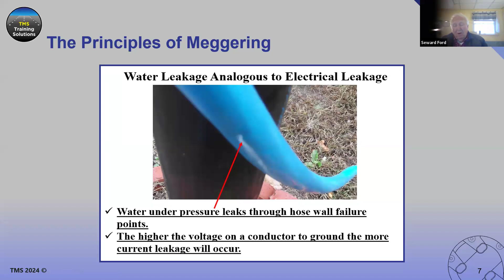We measure circuits to determine if over time there has been any reduction in the insulation or resistance capability of the airport lighting cables. Is that insulation changing over time? That is our responsibility: to get out and measure the circuits at dedicated times and to gather a history of what is happening. We base many of our decisions and our actions on the trend that we see developing as we measure the circuits over time on a specific schedule.